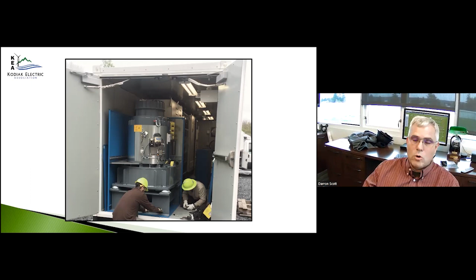So these flywheels basically directly couple electrically with the crane when it's in operation. When the crane needs power, the flywheels inject that power to it. When the crane sends power back to the grid, the flywheels grab that power back and spin back up, so our system sees very little of what's happening. These machines have been awesome - very low maintenance, great machines all the way through. They're an ABB Piller flywheel system, owned by Hitachi now, but that was originally who they were.